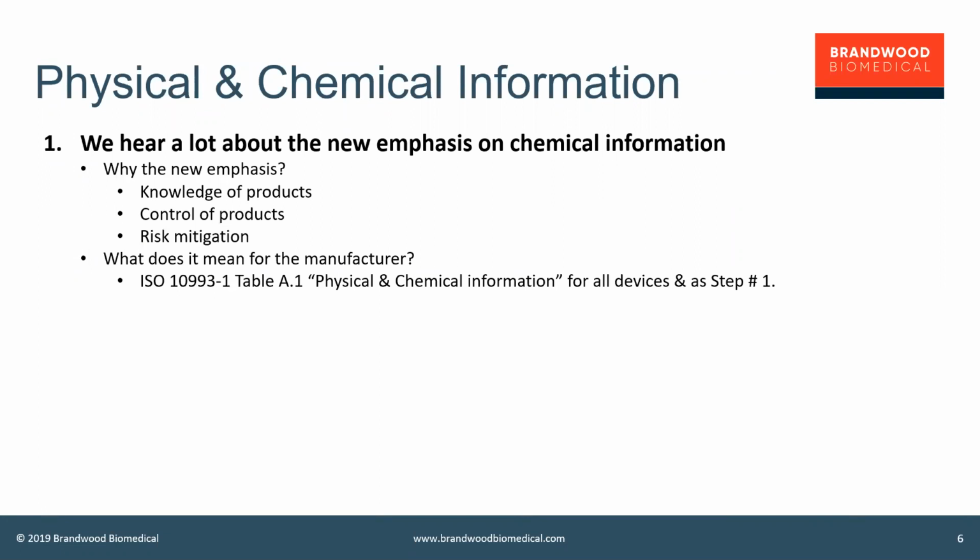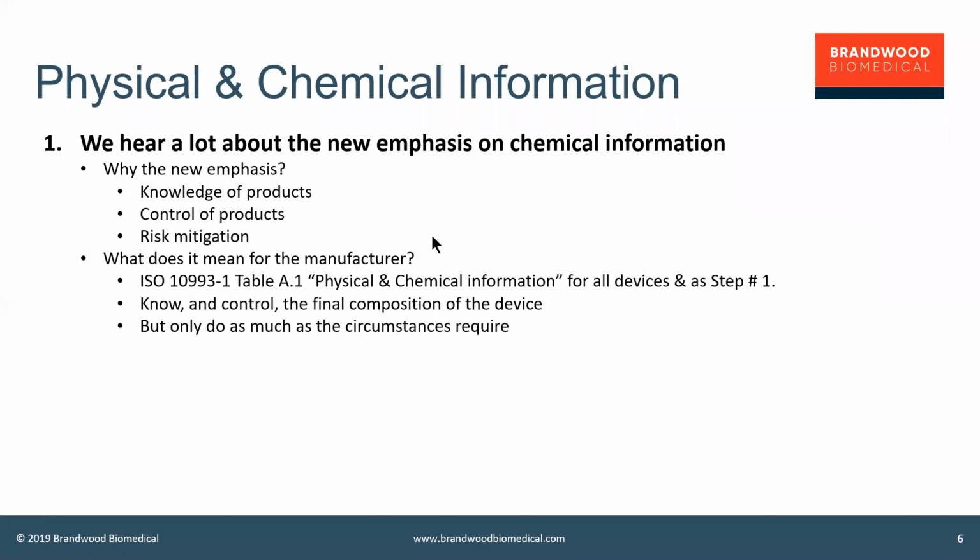Make sure that you find out or that you know or that you're able to control the chemical and physical characteristics of the device before you begin any other parts of the biocompatibility evaluation. Again, know and control your final composition.